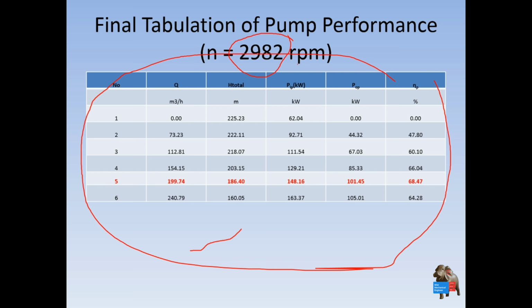Let's say this constant speed is the motor chosen, or the speed that you are offering to the customer. This is the design speed of the motor, and unfortunately the speed will not always be the same from motor to motor. It depends on efficiency and so on, but you need to make a pump performance test at the constant speed. You never get to constant speed, but you transfer theoretically to constant speed. So you have a new table here.